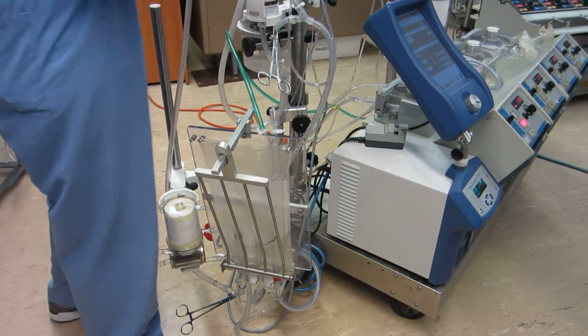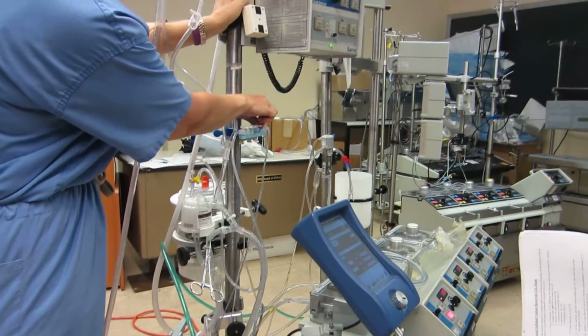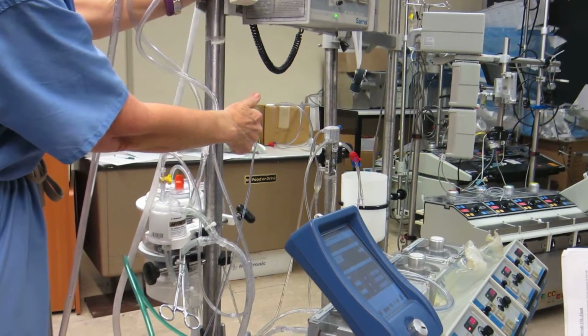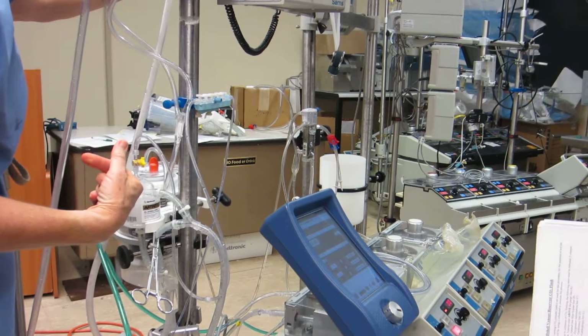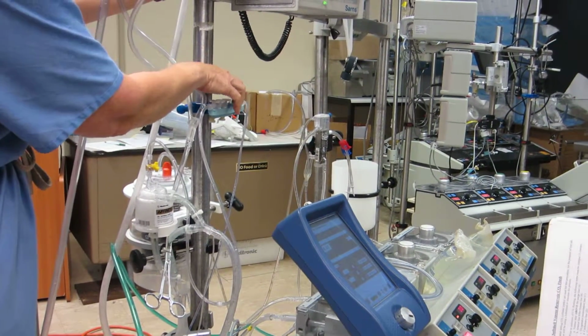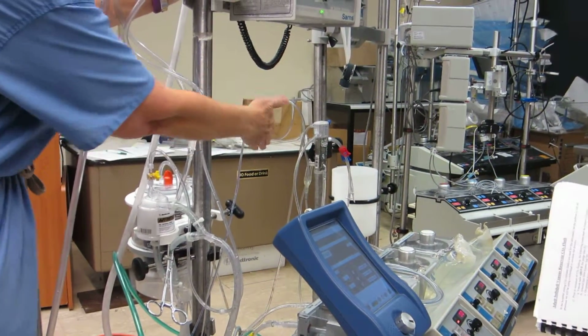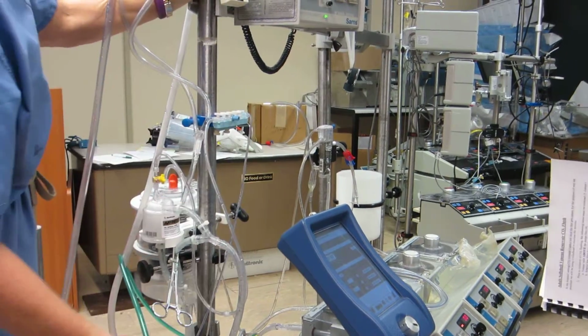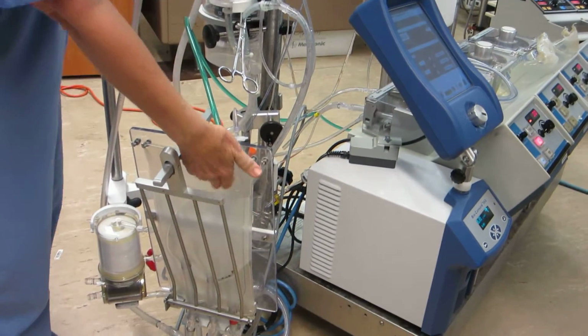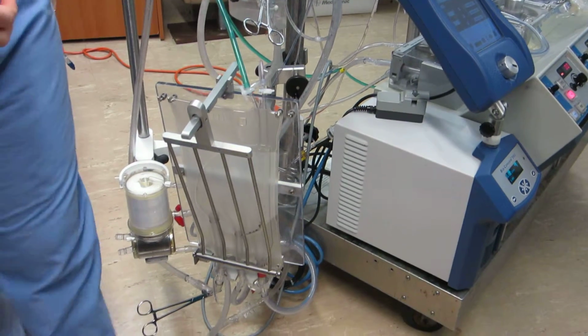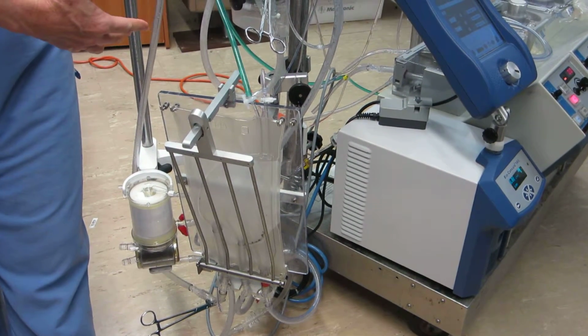don't have a vent. So I'm going to go to my manifold line and I'm going to open to the arterial line filter, close to the arterial line filter, but open to atmosphere, and that's what I'm using as my vent. Okay? And the reason you want to kind of blow the bag up with the CO2 is you want to test the integrity of the bag.